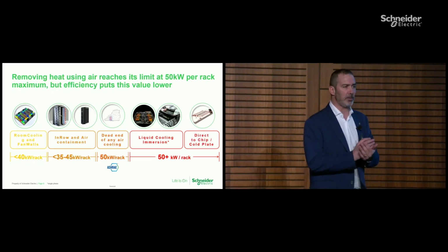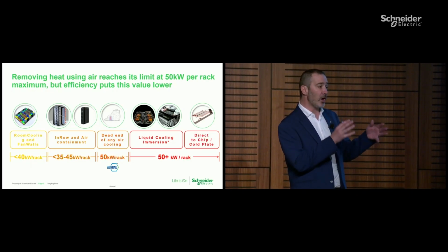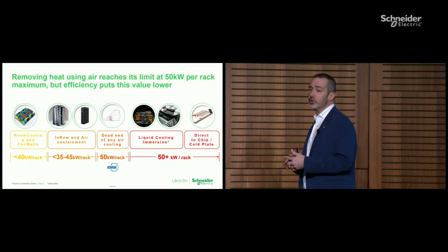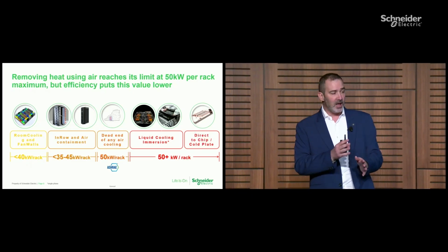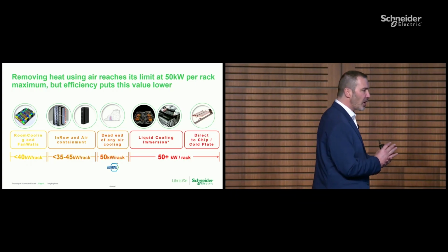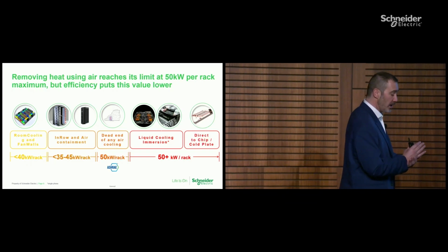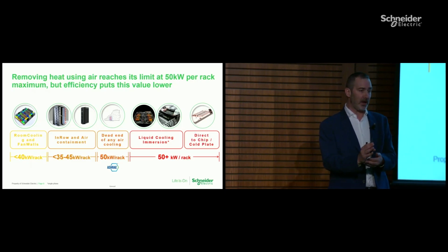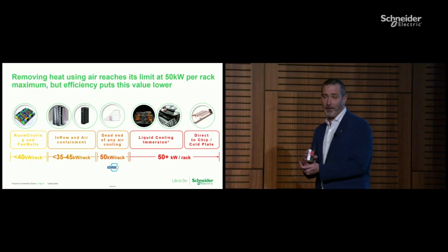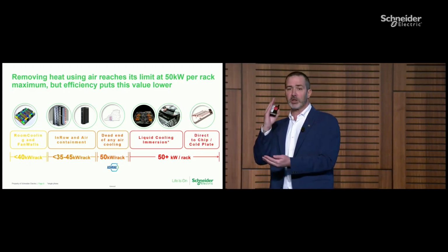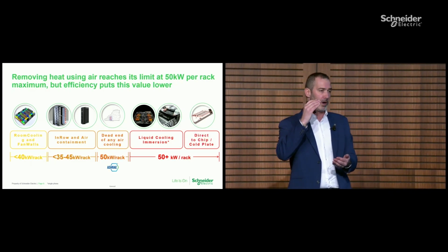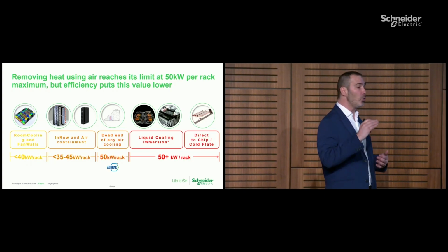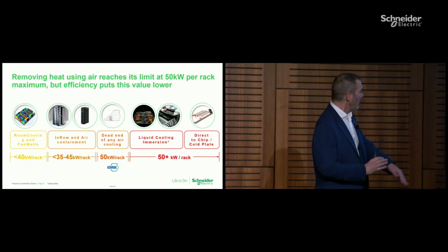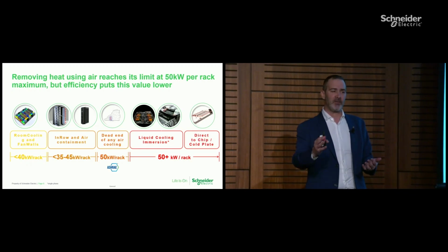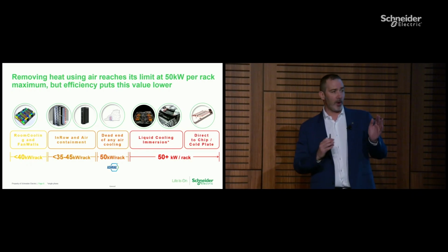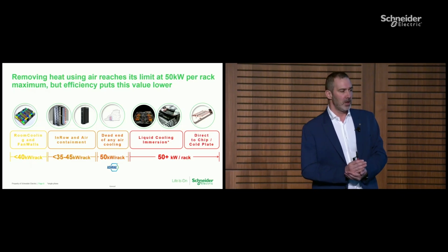Because below 50 kilowatt per rack, you can use air cooling. It's a pretty efficient solution for that, but back in 2020, ASHRAE introduced a new guideline mentioning that at 50 kilowatt per rack, the supply air temperature to dissipate servers for more than 50 kilowatts per rack needs to move to 21, 24 degrees Celsius. Lower than that can be 27 as recommended. 50 or above, it must be 21.